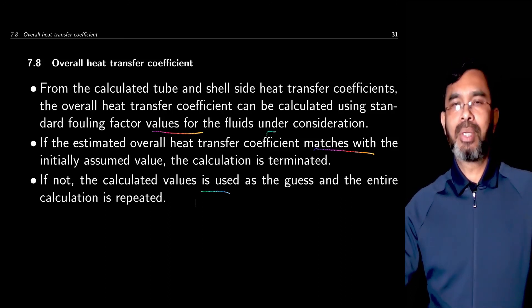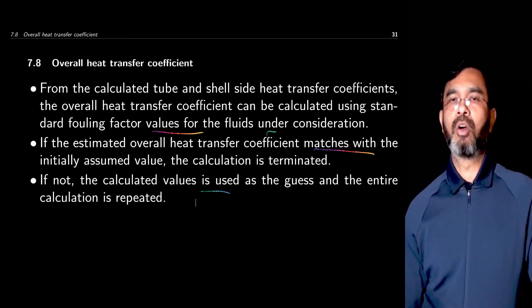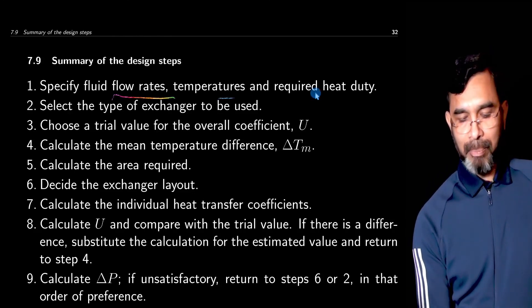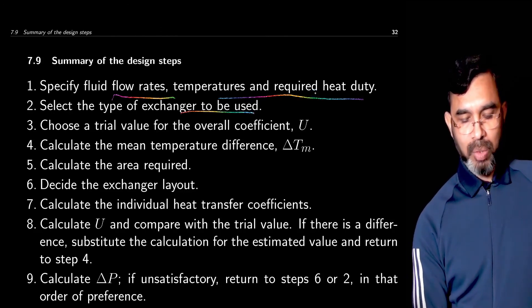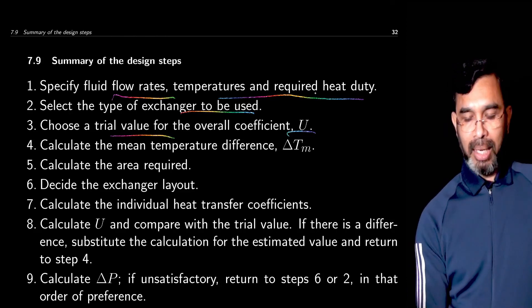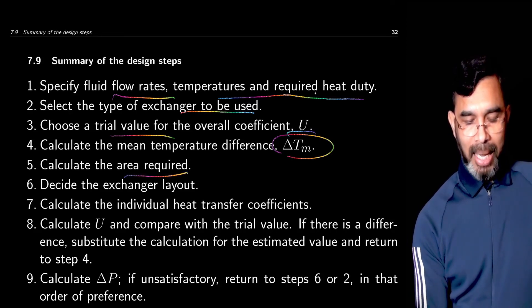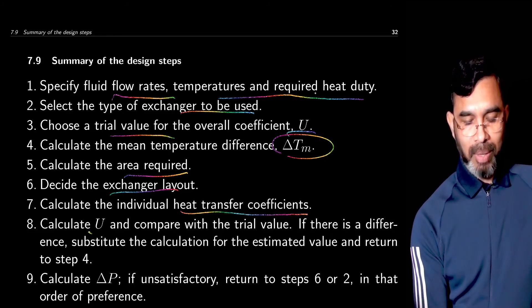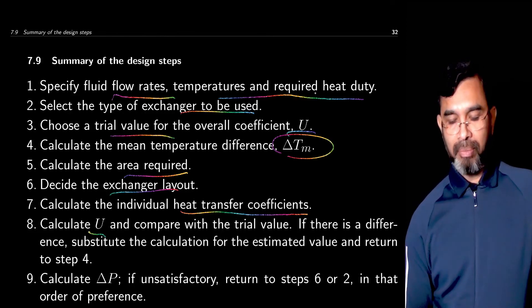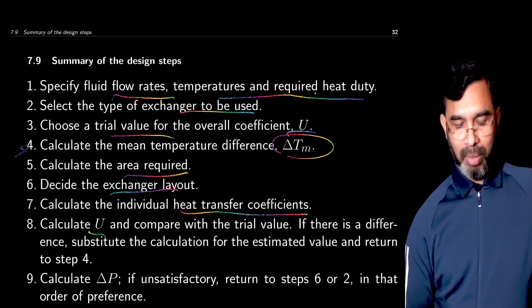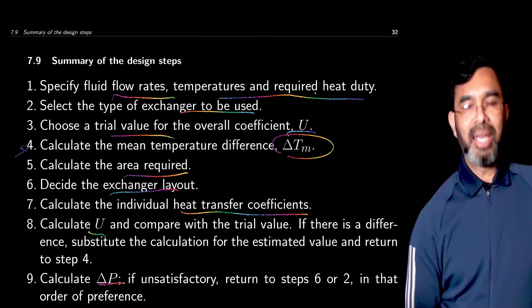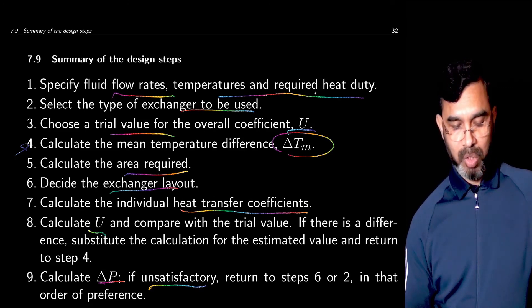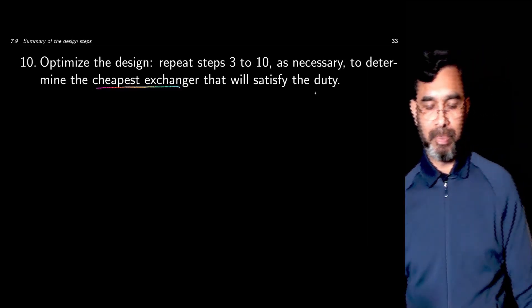We will look in detail at how to calculate the tube side, shell side, and overall heat transfer coefficients. The procedure for heat exchanger design is summarized as: specify fluid flow rates, temperatures, and required heat duty; select the type of heat exchanger and choose a trial value for the overall heat transfer coefficient; calculate the mean temperature difference to get the required area; decide on the exchanger layout and calculate individual heat transfer coefficients; calculate the overall heat transfer coefficient and compare with the trial value. If there is a difference, repeat the calculation. Once converged, also calculate the pressure drop delta P. If delta P does not meet process requirements, choose a different configuration and repeat. Finally, optimize the design from a cost perspective.